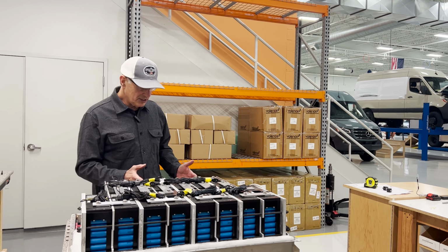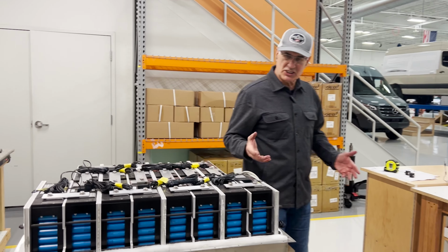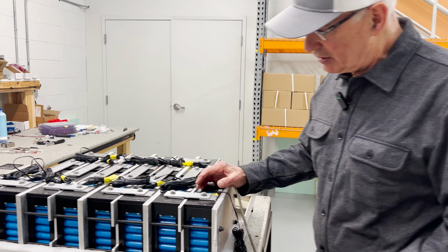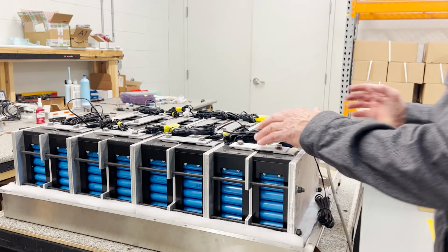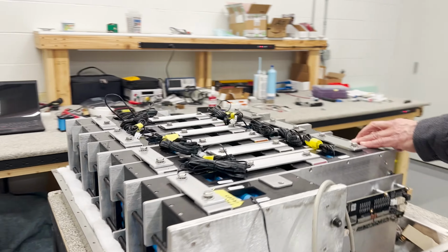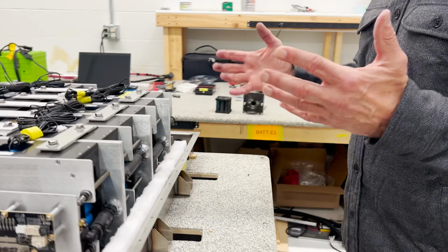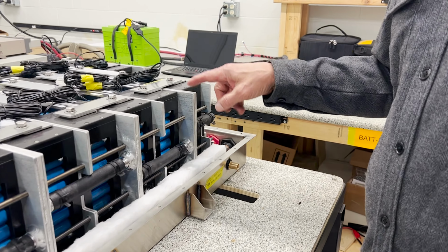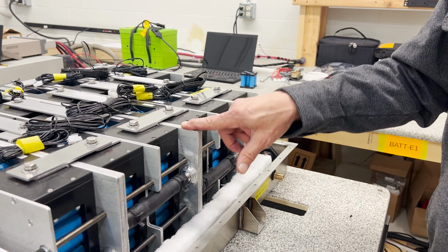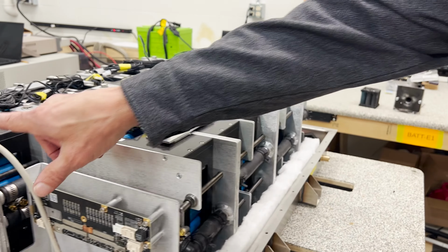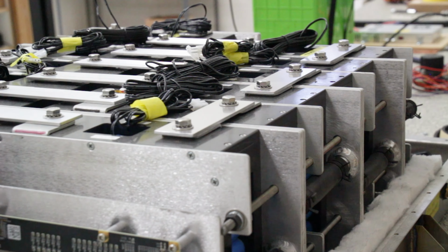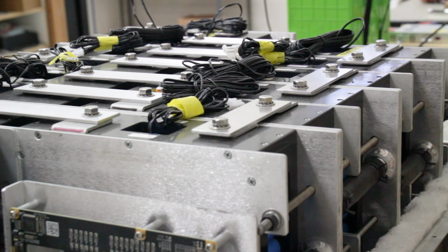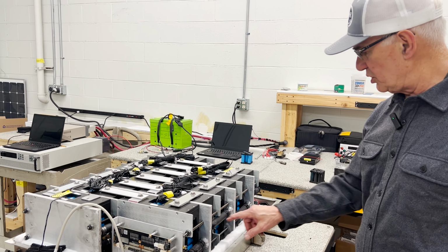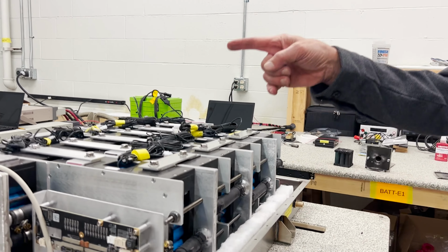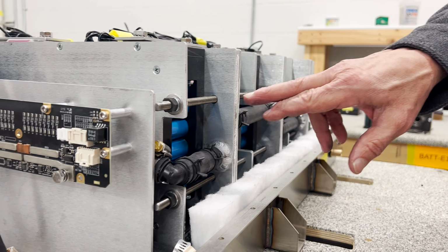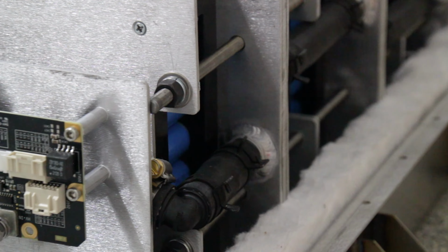So when you're looking at this, the things that make it so expensive are the batteries themselves, but on this side there are heat exchangers internally designed and manufactured in our metal shop. There are five heat exchangers that can be heated or cooled with liquids. These are the hoses that connect the heat exchangers, in a serpentine path - these are plate-to-plate heat exchangers.